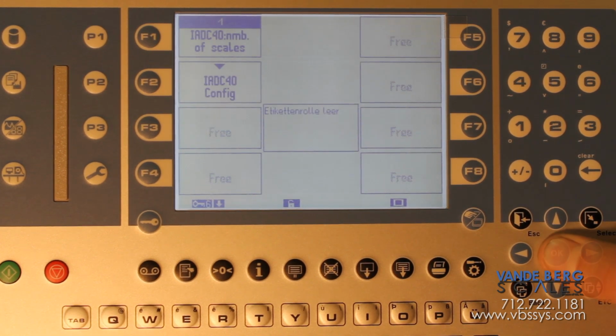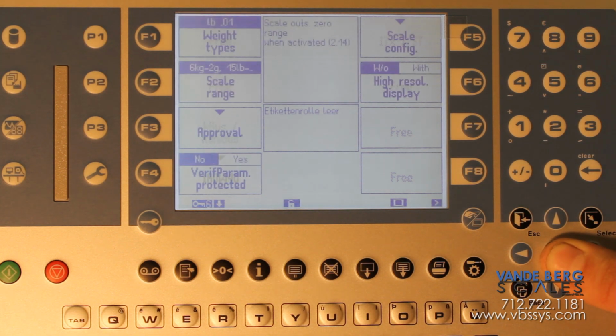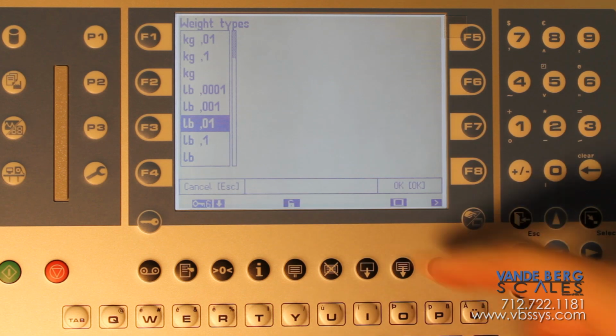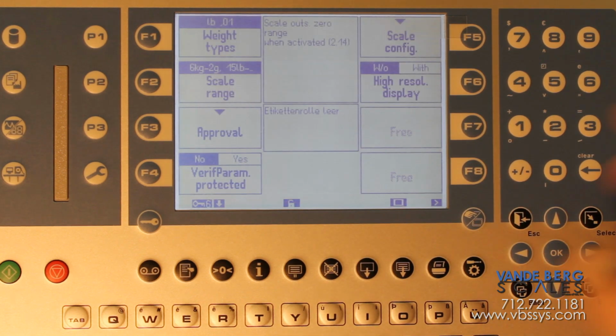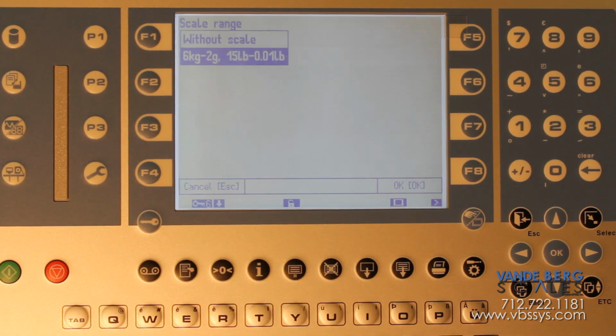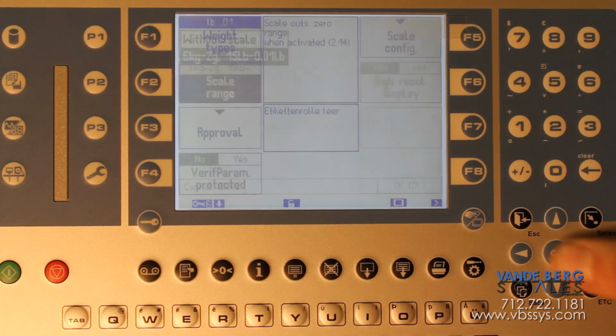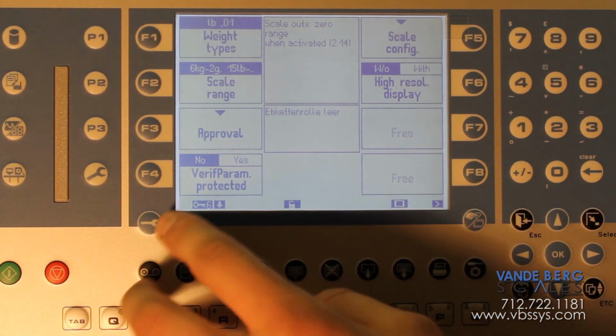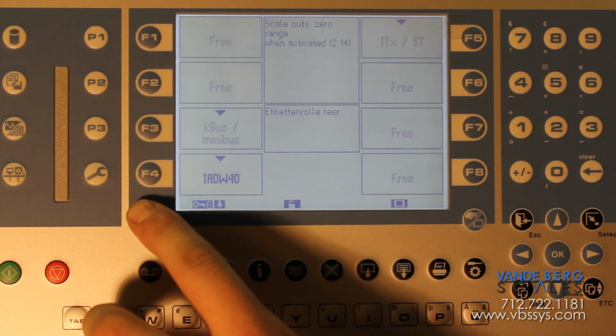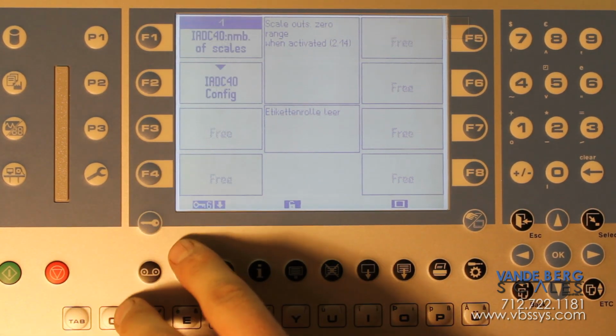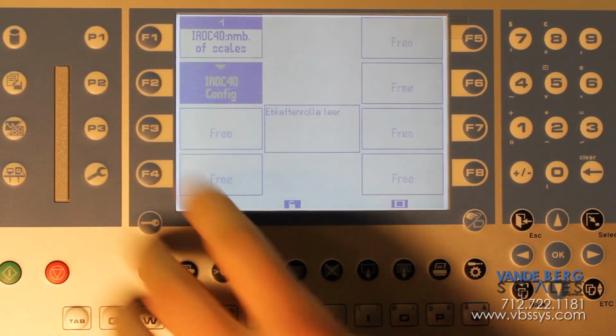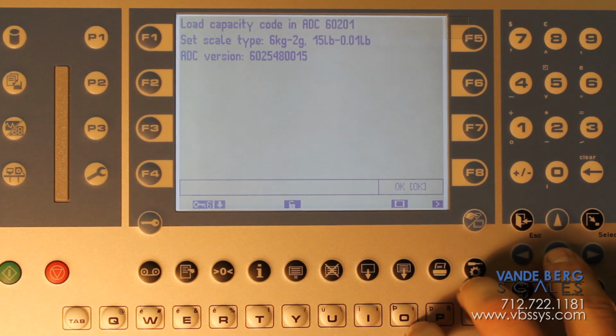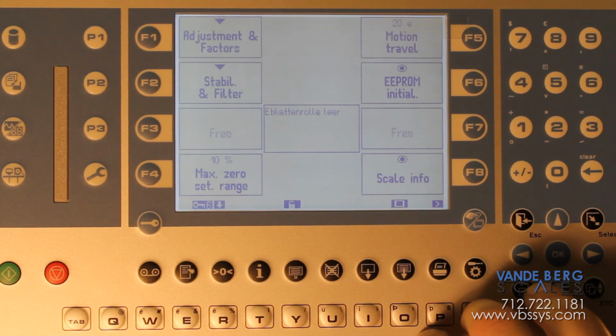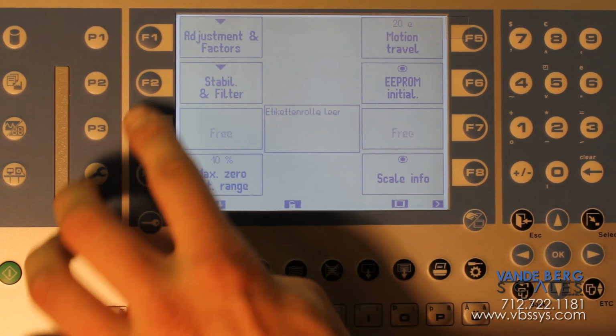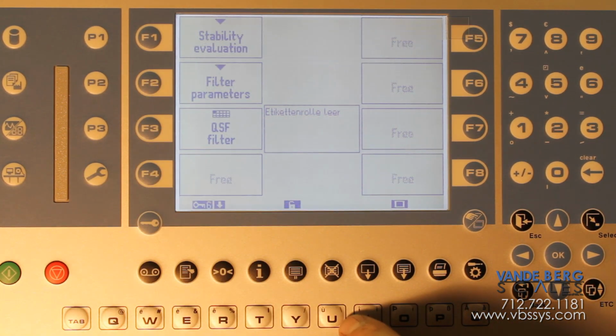We can then go back with the OK button, go to weight types, make sure this is pound by 0.01 and the scale range is set to 15 by 0.01 pounds. Now we'll go into the scale configuration again, IADC40. We'll go into the IADC40 configuration, accept this window. Now we'll hit the stable and filter button, which is F2.